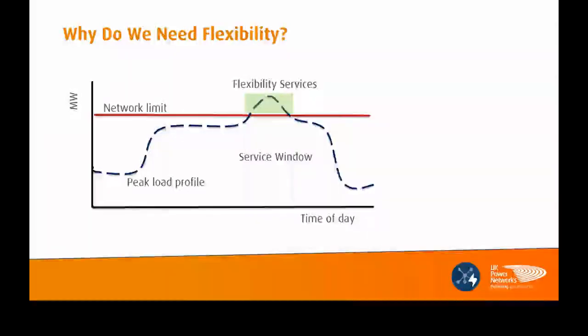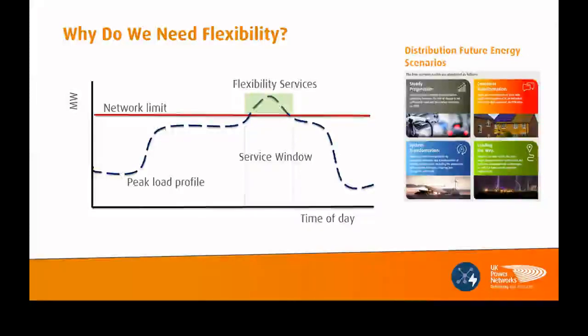The way we do that is we use forecasts to identify when the peak may occur, which we call the service window. It could be from November to February, 4 to 6 p.m., for example, where you have to be available. When the peak demand actually breaches the limitation, we would send an instruction for you to deliver the service.